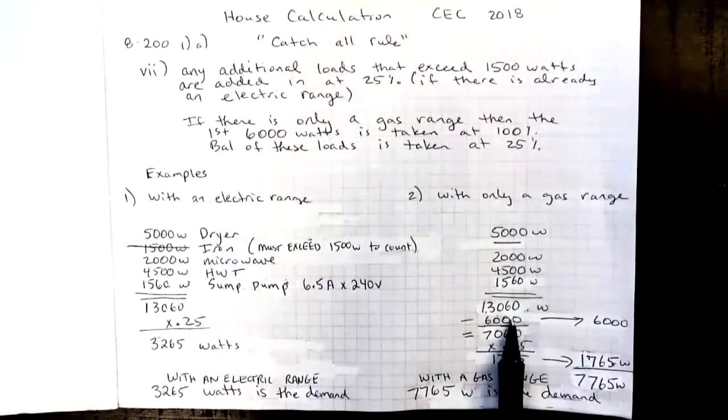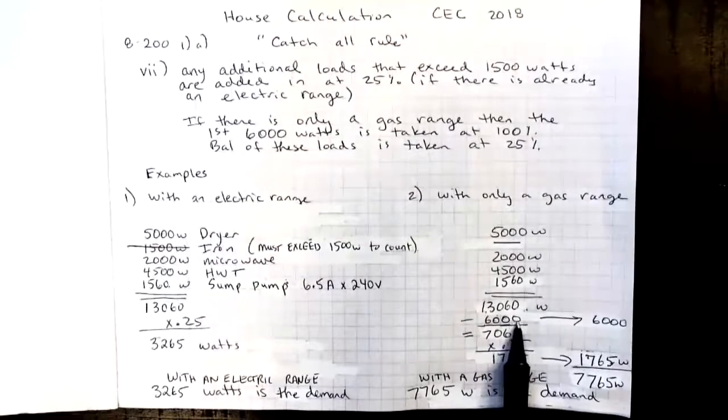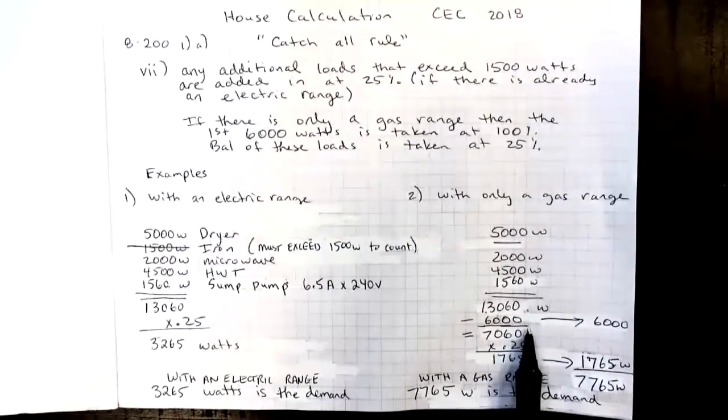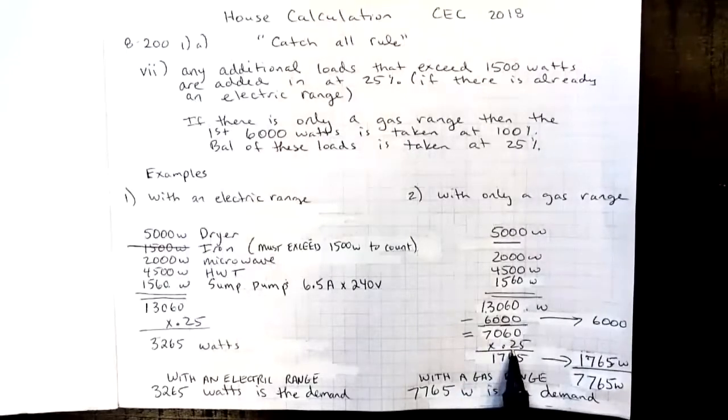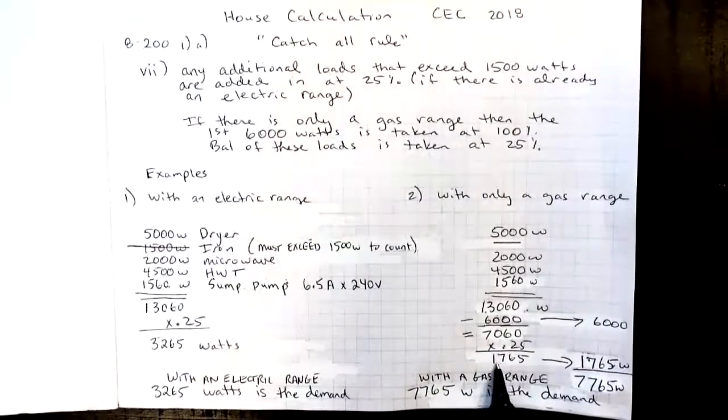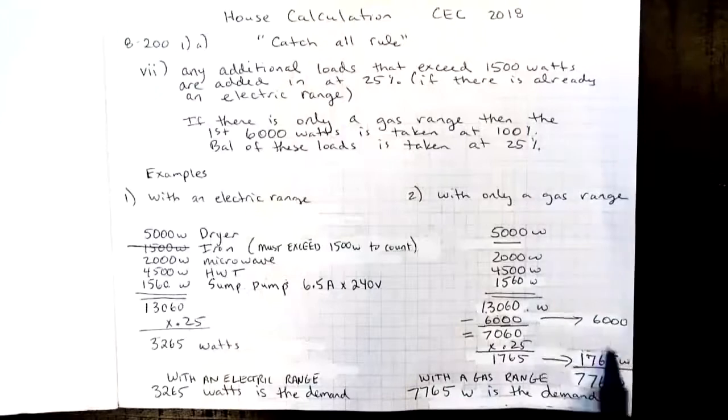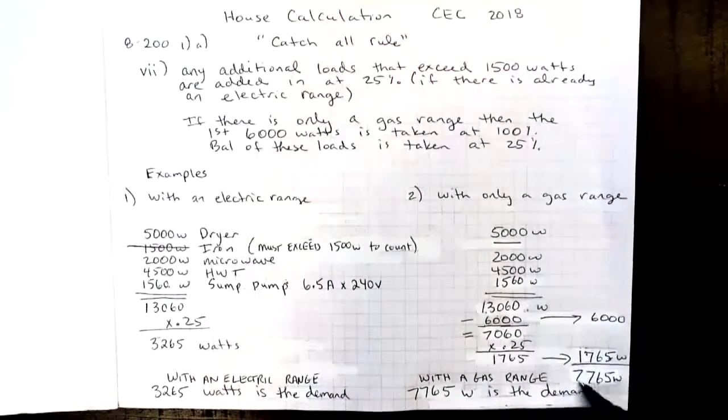This kind of replaces the fact that we don't have a range calculated in, because we had a gas range. Then we subtract that out of our total, and we end up with 7,060. That 7,060 is going to go in at a demand factor of 25%. So we're going to take that 25% over here.